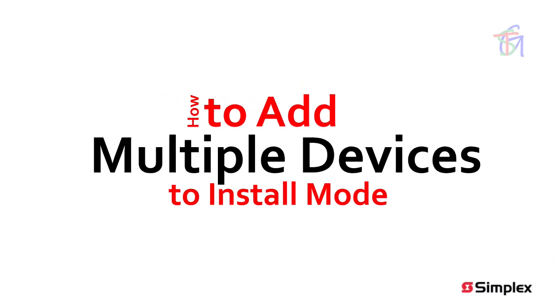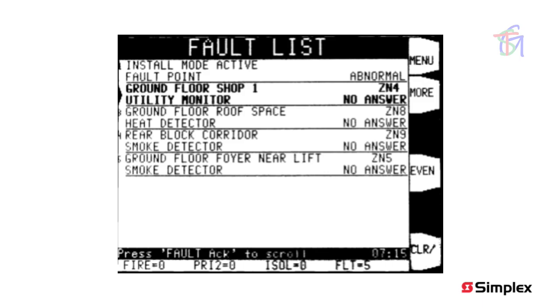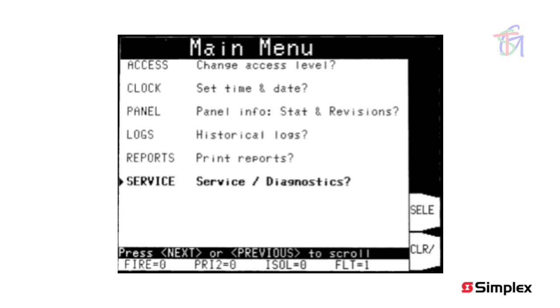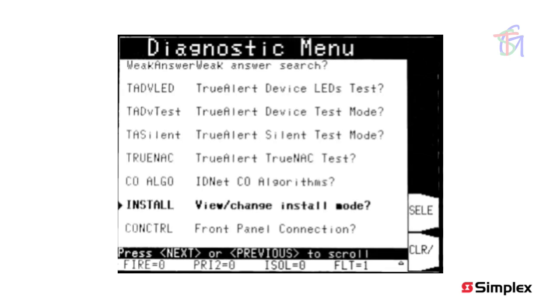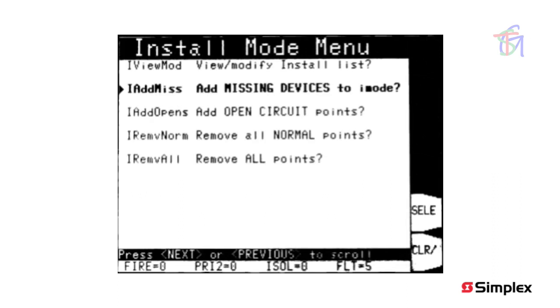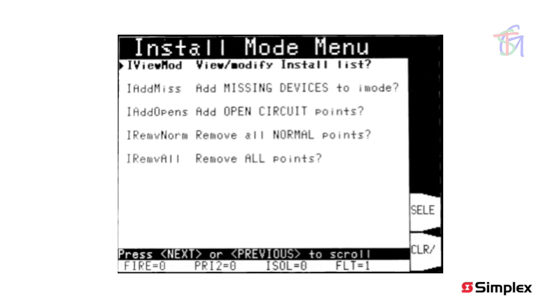Where there are many missing devices all producing faults, there are simple ways to quickly add these to the install mode list in bulk. Note that this requires being logged in at level 3. Press menu, then scroll the highlight to the service or diagnostics option and press the select soft key. In the diagnostic menu screen, scroll down to the install mode option — there are many diagnostic options, so using page down to jump a screen at a time will be faster. Press the select soft key to select it. In the install mode menu, move the highlight to the add missing option and press select. The panel will take a few seconds to search for all missing devices and add them to the install mode list. Note that the fault count changes from 5 to just 1 — the single remaining fault is the install mode fault.